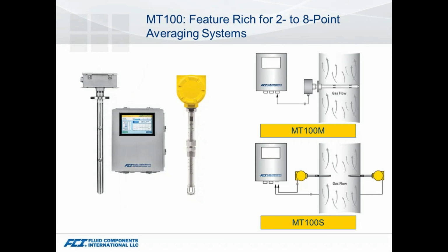This was our more traditional style, a little bit difficult to deal with at times, because now instead of compression fitting options or packing gland options, we're looking at either a fixed flange or a 2-inch MPT connection. So given that, you've got to really pay more attention to the details of the installation. And with these multi-point probes, these larger ones where we put 2 or more points on the single mast, you also have to be thinking of access and orientation. Do I have enough room to clear that sensor to get it across the duct or pipe that I'm putting it into?